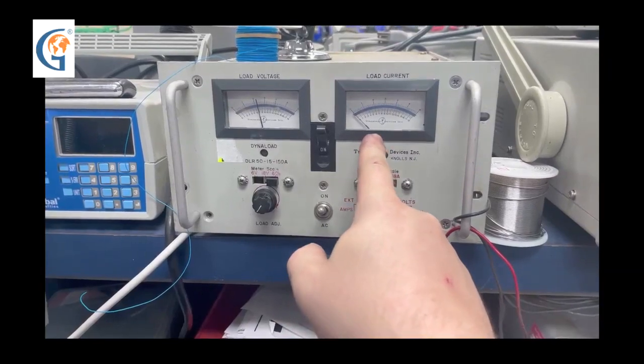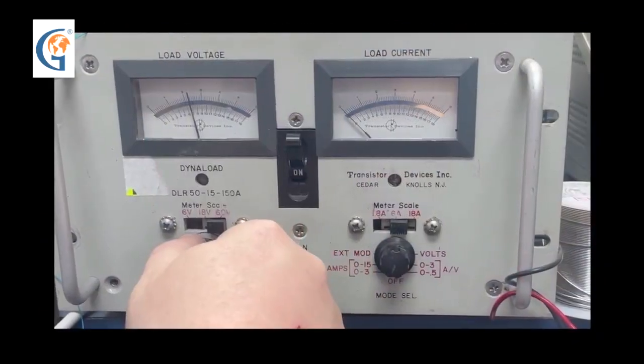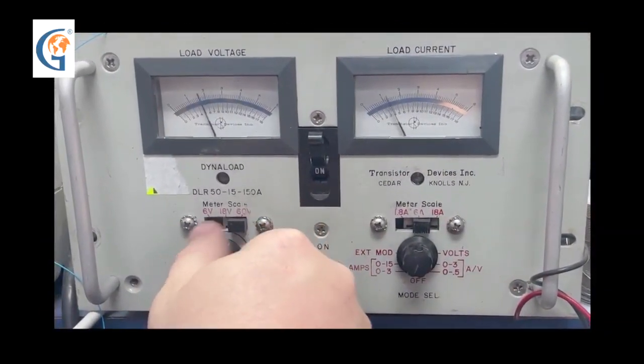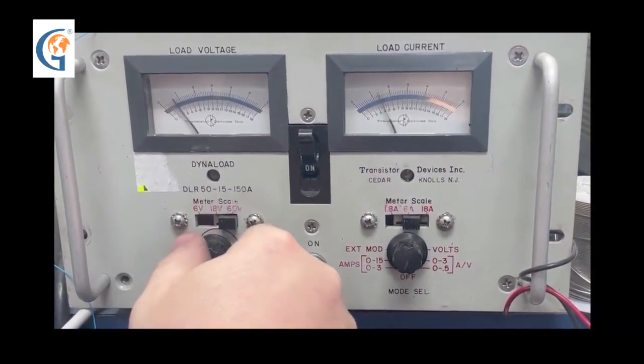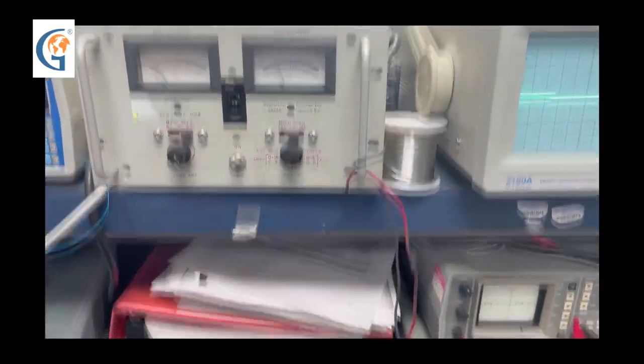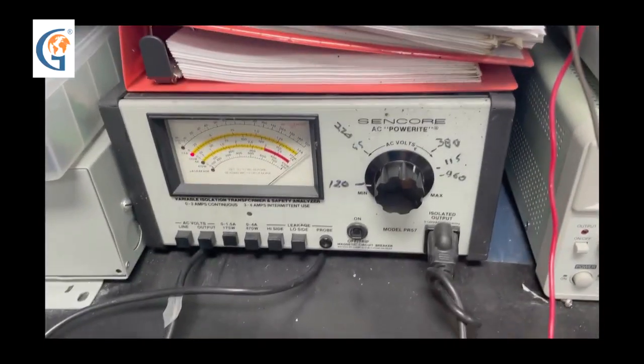Now, we'll apply the load at 5 amps. With the full load applied, we are no longer getting our output. Since we already changed the caps, we suspect a problem in the PWM circuit.